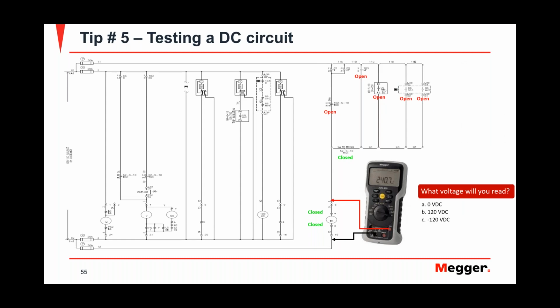Let's say right now you're checking the voltage on your trip coil, and all these contacts are open, this one is closed, and you put your multimeter to measure the voltage across the trip coil. What voltage would you see? Would you see 0 volts, 120 volts, or minus 120 volts? The answer is 0 volts, because you've got positive DC coming up to here, and it stops at the contact. By your negative DC voltage, there is no voltage drop on the trip coil. There's no current flowing. Therefore, the voltage drop across that trip coil at this moment is 0. So you should read 0 volts.